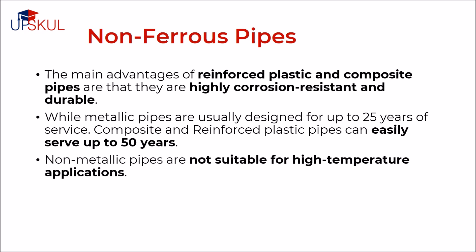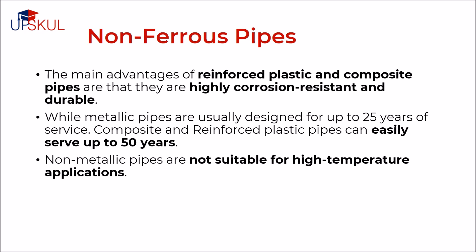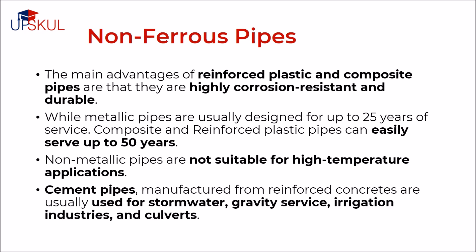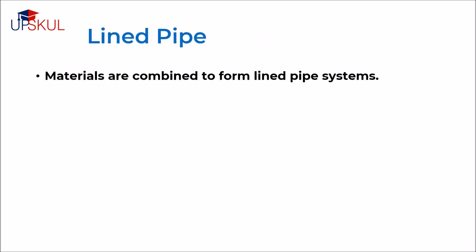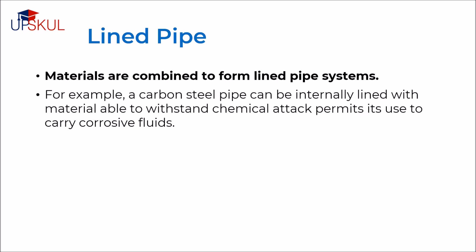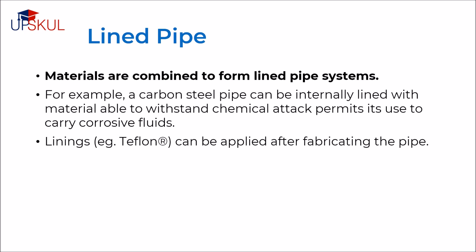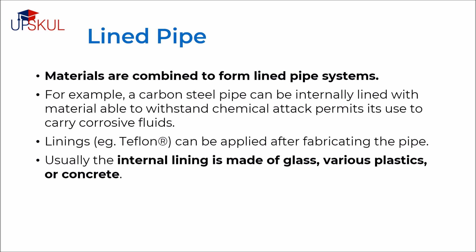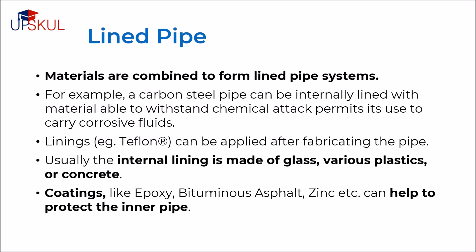However, their main limitation is temperature. Non-metallic pipes are not suitable for high temperature applications. Cement pipes manufactured from reinforced concrete are usually used for storm water, gravity service, irrigation industries and culverts. Some materials discussed just now have been combined to form lined pipe systems. For example, a carbon steel pipe can be internally lined with material able to withstand chemical attack, permitting its use to carry corrosive fluids. Linings like teflon can be applied after fabricating the pipe. Usually the internal lining is made up of glass, various types of plastics or concrete. Coatings can also be applied such as epoxy, bituminous, asphalt, zinc, etc. which can help to protect the inner pipe.